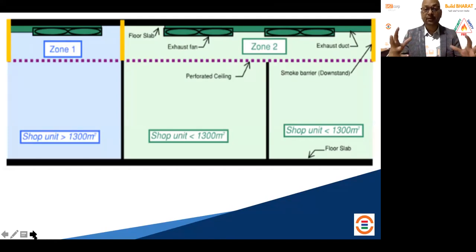That's the more scientific way to plan how my smoke is going to travel and how I'm going to restrict it, typically in the atrium area. It's a very difficult area to understand the smoke. Usually in an atrium you only have smoke exhaust fans on top, maybe one or two fans, that's about it. But where exactly? Is there a smoke barrier on the atrium side also, where maybe the food court area is connected? You might have an atrium lobby that isn't separated from the lobby and atrium area with a sprinkler system or water curtain system.